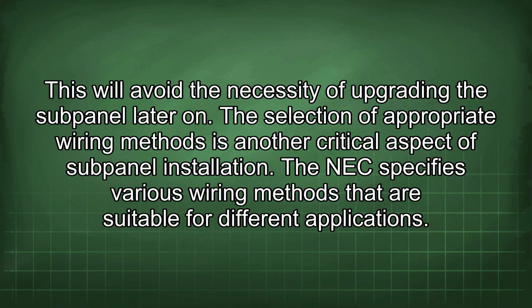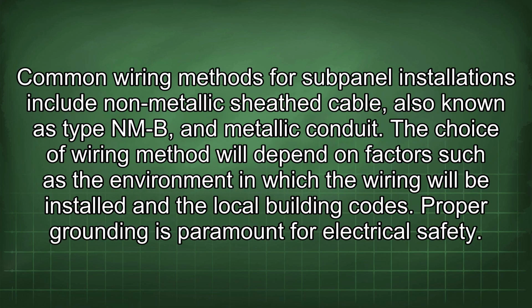The selection of appropriate wiring methods is another critical aspect of subpanel installation. The NEC specifies various wiring methods that are suitable for different applications. Common wiring methods for subpanel installations include non-metallic sheathed cable, also known as type NM-B, and metallic conduit. The choice of wiring method will depend on factors such as the environment in which the wiring will be installed and the local building codes.